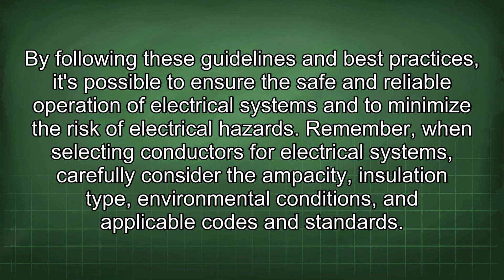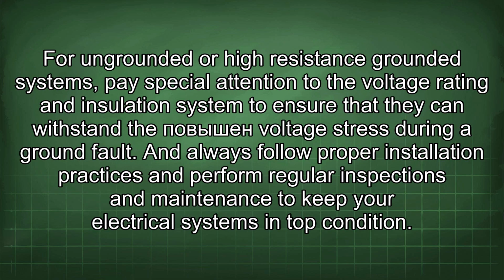Remember, when selecting conductors for electrical systems, carefully consider the ampacity, insulation type, environmental conditions, and applicable codes and standards. For ungrounded or high-resistance grounded systems, pay special attention to the voltage rating and insulation system to ensure that they can withstand the increased voltage stress during a ground fault. And always follow proper installation practices and perform regular inspections and maintenance to keep your electrical systems in top condition.